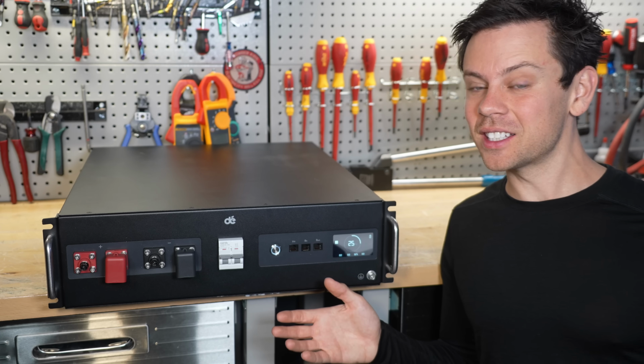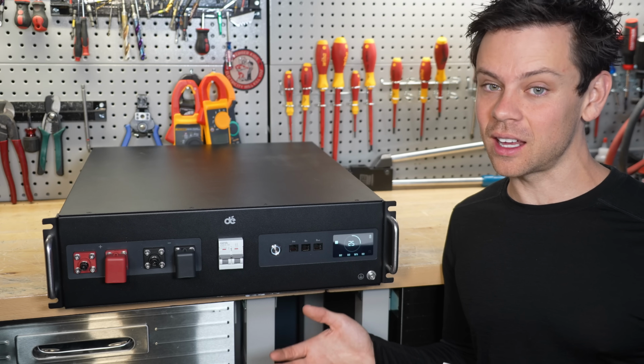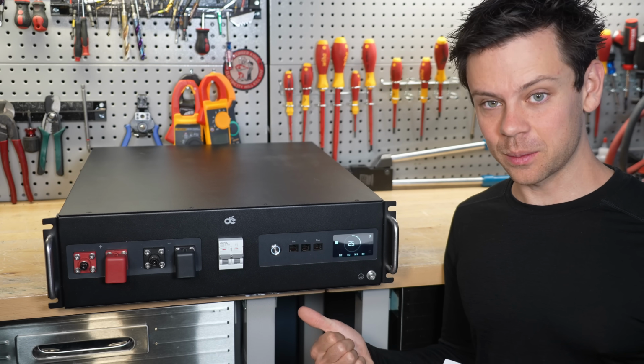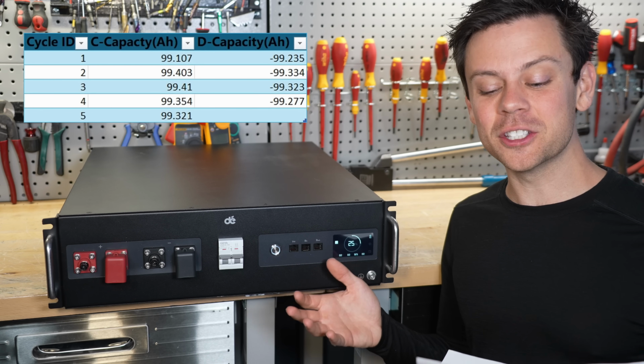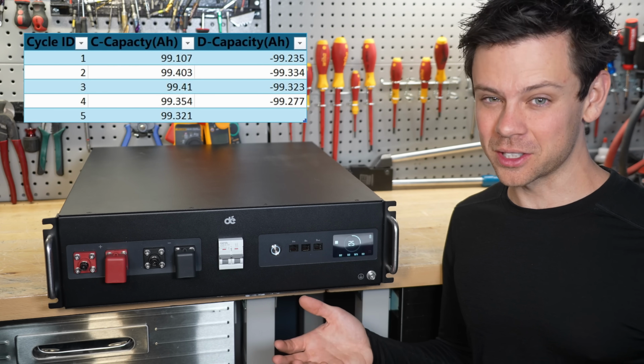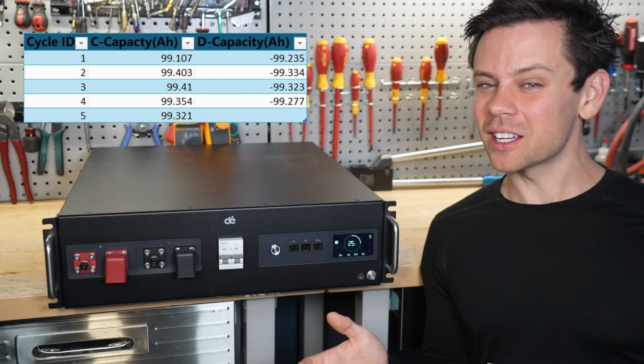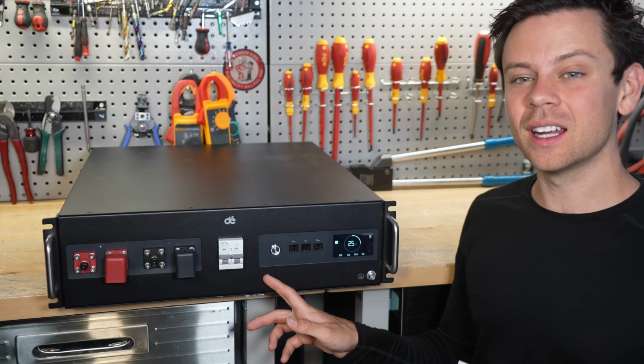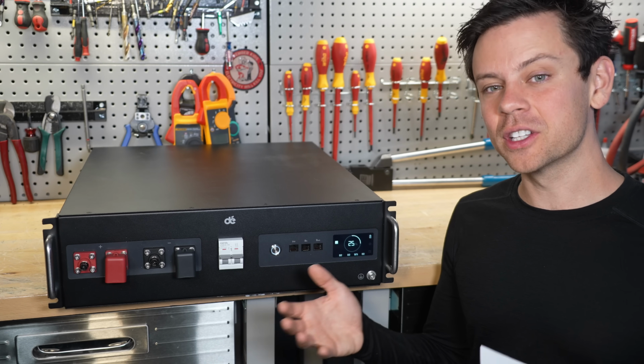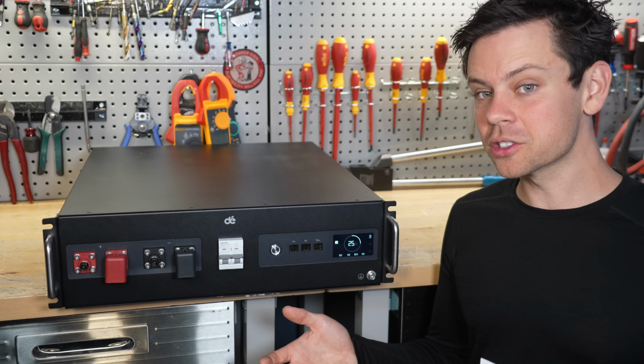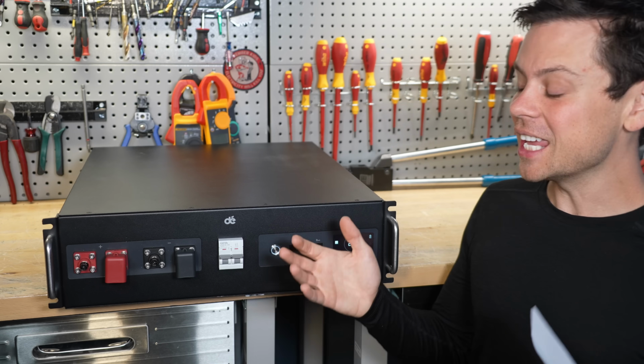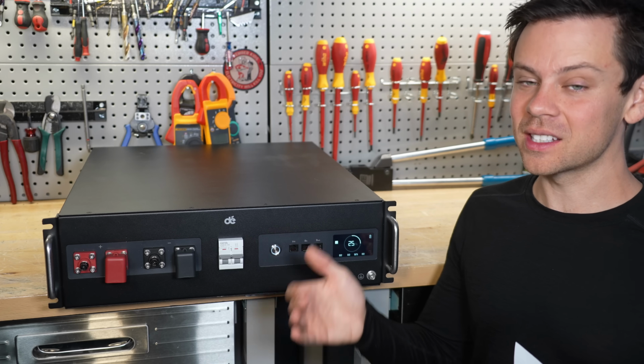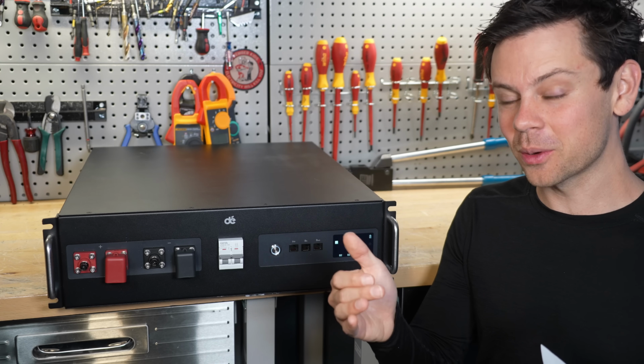The first test I did for the last few weeks was capacity cycle testing with 50 amps, and I pulled between 99.2 and 99.3 amp hours. No matter how many times I cycled it or tested it or left it at a high state of charge, it wouldn't increase or decrease. A lot of the older server rack batteries had this issue. Even the old EG4 server rack batteries stayed at like 99.5 amp hours forever.